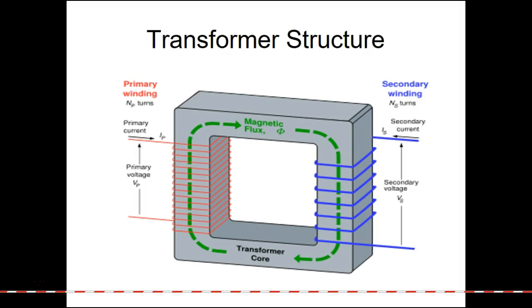So what determines... so what you'll see is your high voltage side, the windings will be really, really thin because they have less current.